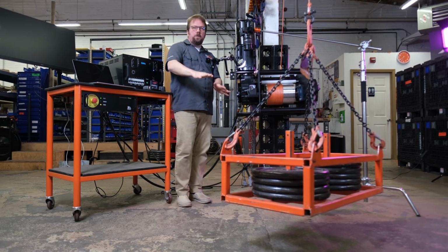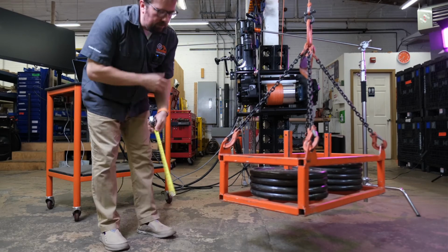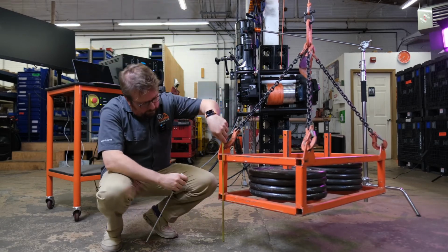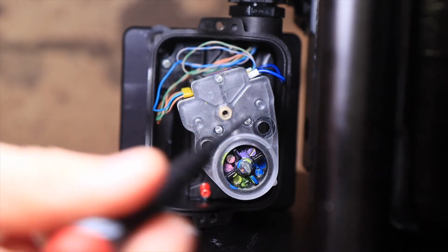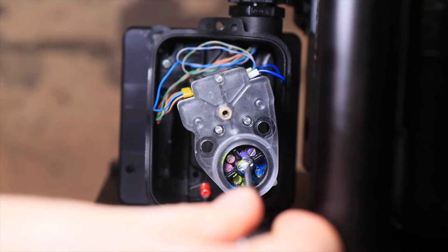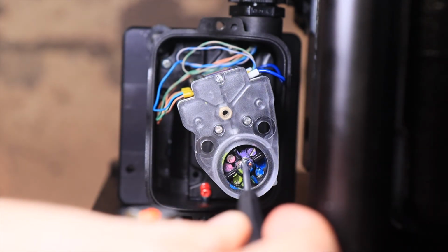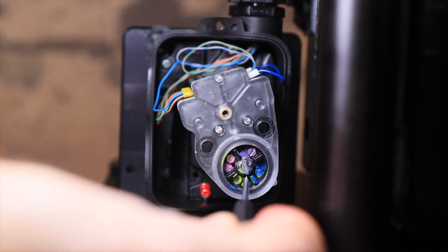Okay, I'm gonna hold this as our reverse initial limit position. And I'm gonna take a measurement just to try to keep myself honest. So to set the reverse limit, first thing I wanna do here is loosen the locking screw. That's important. You don't wanna start adjusting the cams with that lock in place because you'll damage the switch.